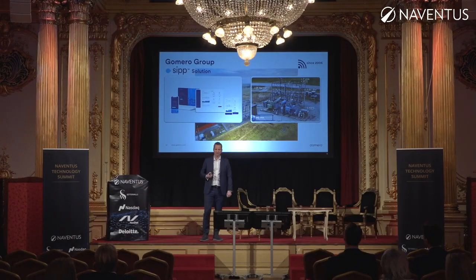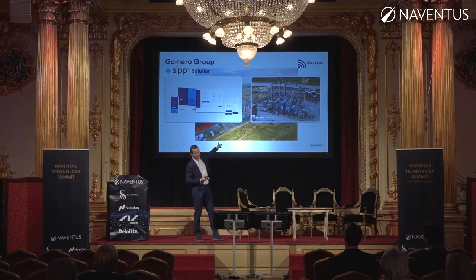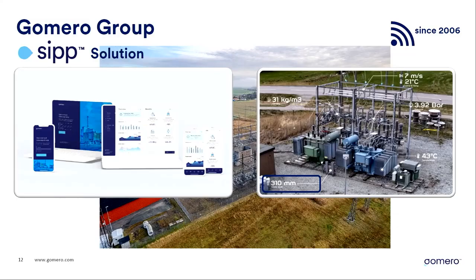And we've been very, very focused on the transformer bund. So the level here, 310 millimeters of water in the transformer bund, so that never goes above a maximum level. And if it does, we pump out automatically. Our measurement cell makes sure that the water is clean.